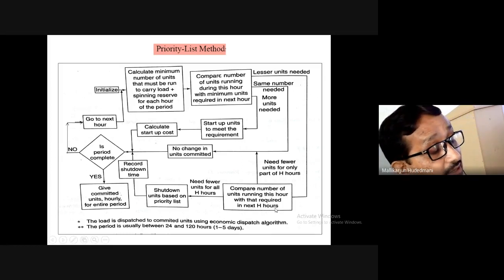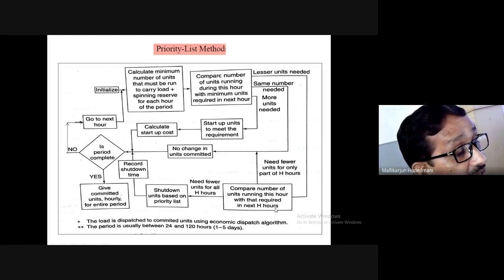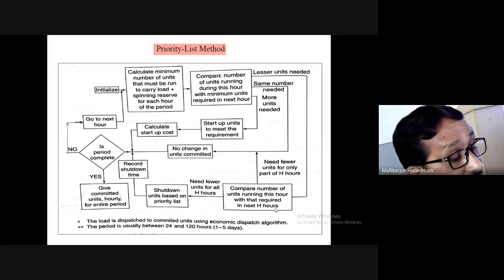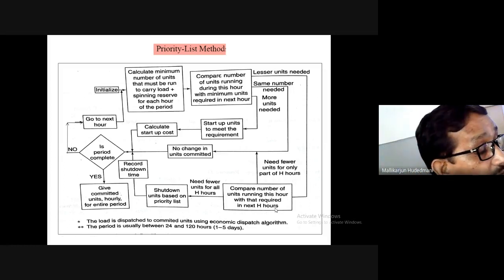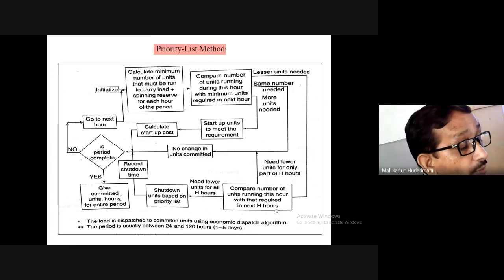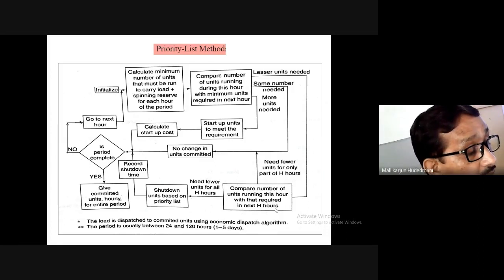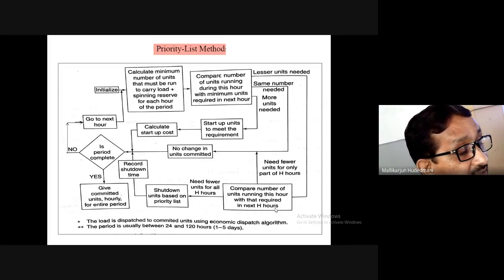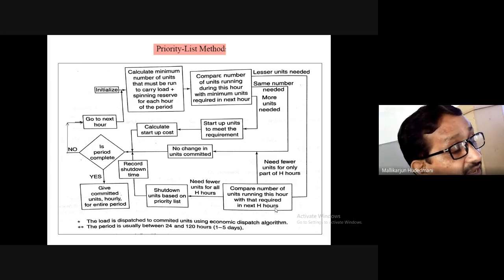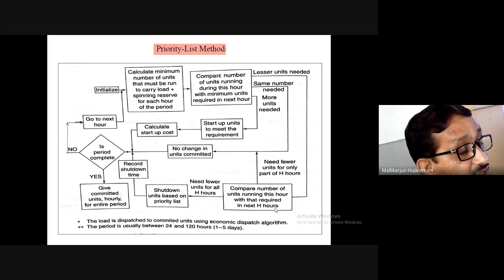This is a decision, because when a decommitment is to be taken, when I want to reduce the generation, the generator needs to be taken out. When I want to take it out, I have two ways: one is to cool down, or maintain at banking. This is what just now we have seen - cooling the generator, or banking it at a certain reduced temperature.